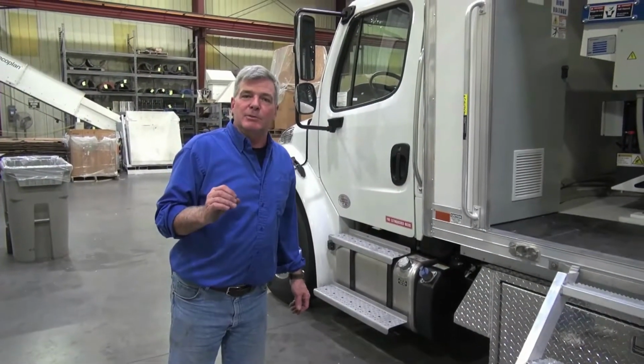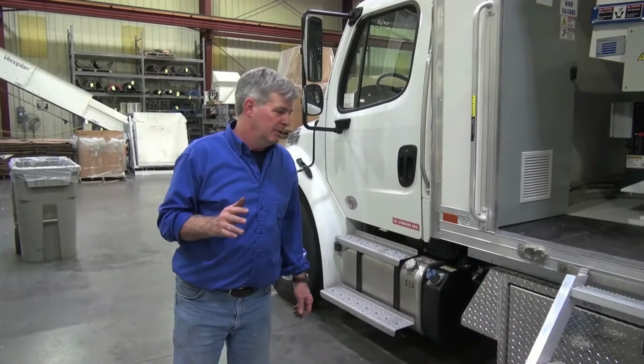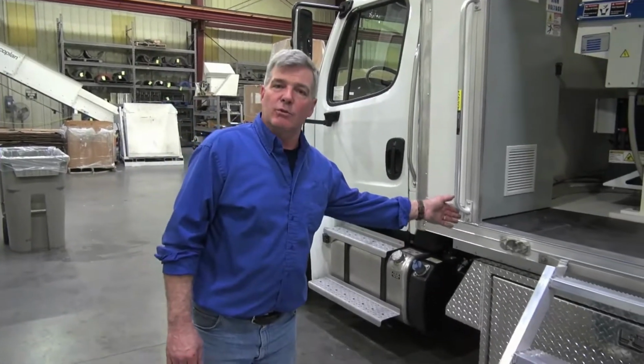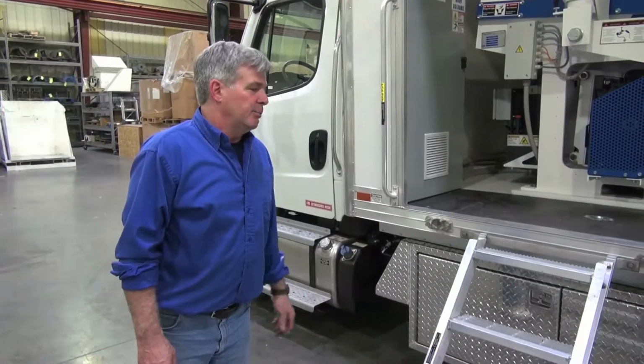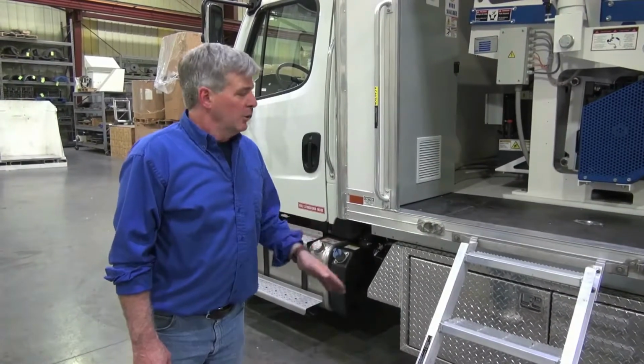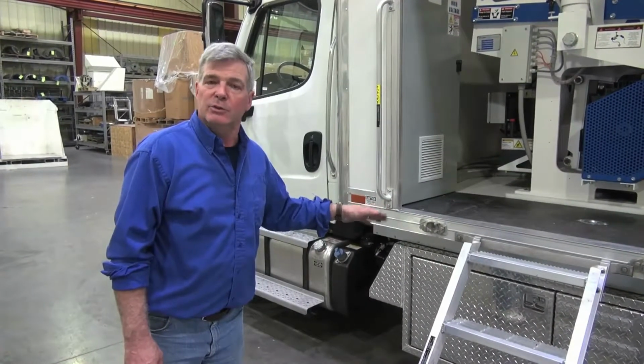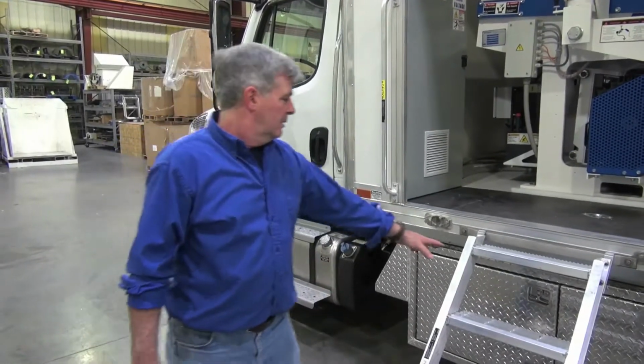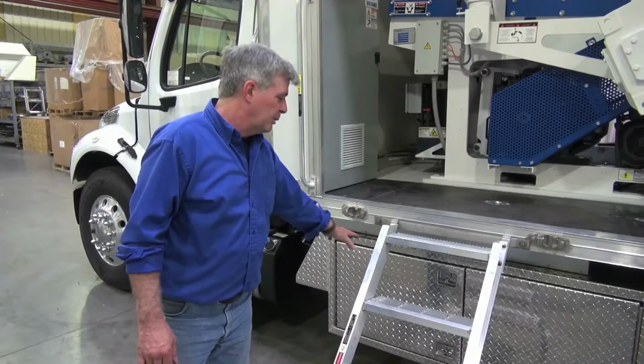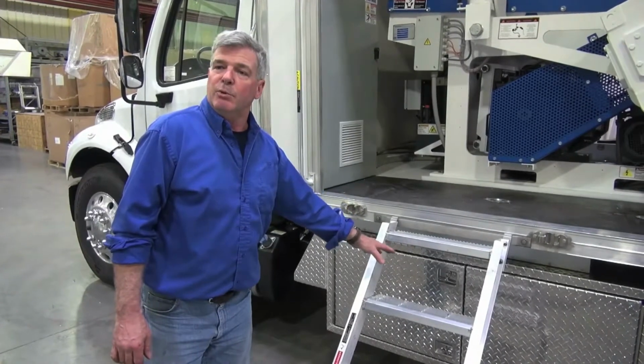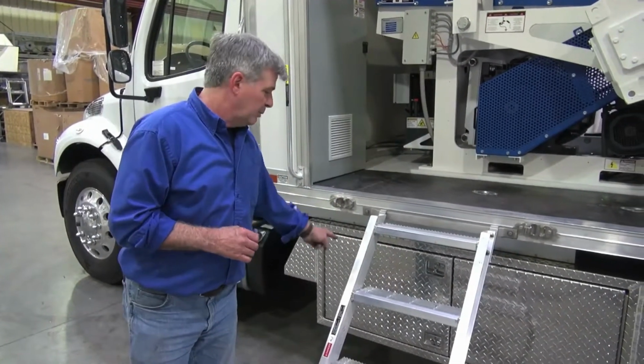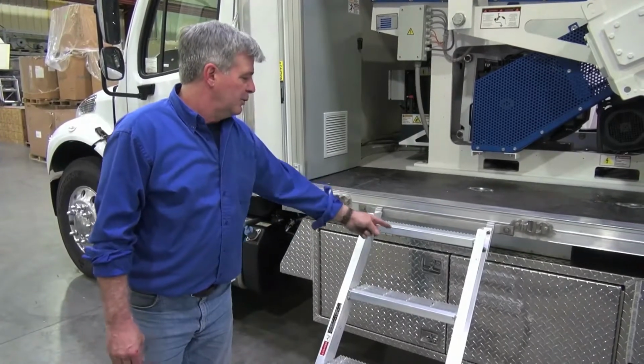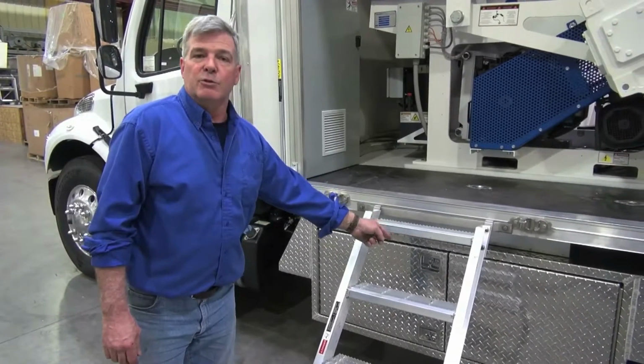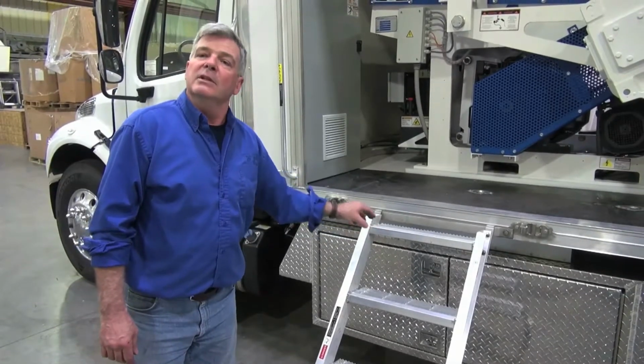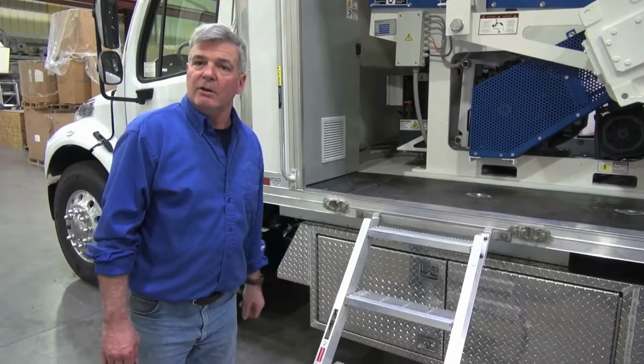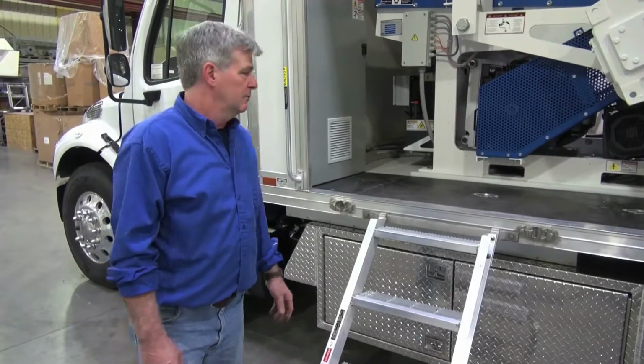Just a few safety tips on the VST 42E to be cautious of. When the PTO is engaged, the drive shaft will be spinning. It's important that when PTO is engaged, nobody gets underneath that truck, as it could cause them harm or death. The generator and the plant power are within this toolbox. It's important that when the disconnect on the plant power is engaged, or the PTO is running and the generator is creating power, that no one goes into this toolbox unless they are a certified electrical technician.